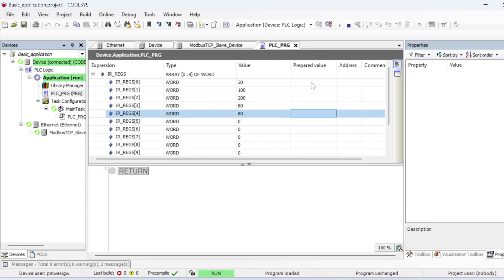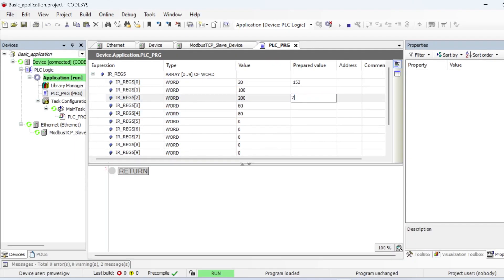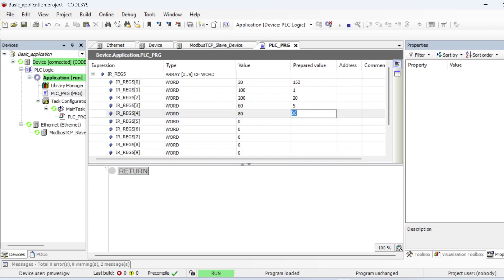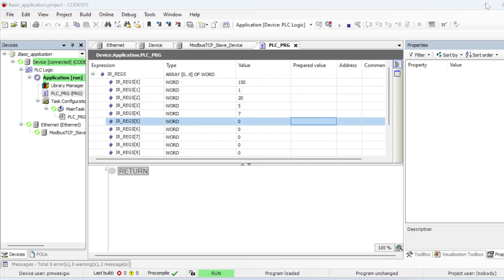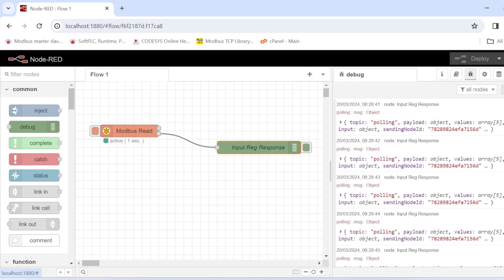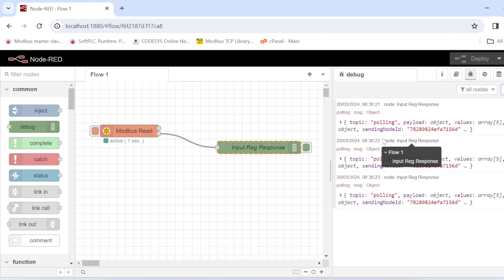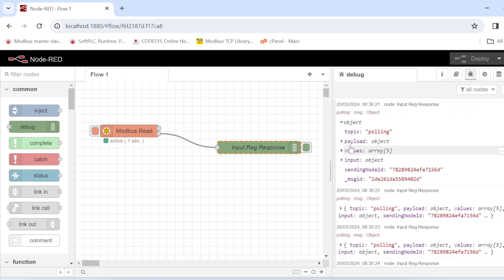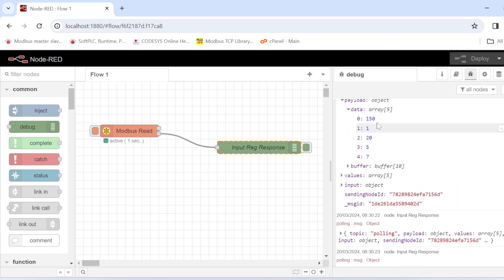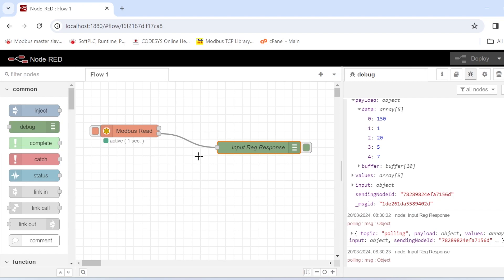We can modify values on the PLC side — for example, changing registers to 150, 20, 1, 5, and 7. Going back to Node-RED, clearing the messages and expanding the new payload, we can see under the data array the values 150, 1, 20, 5, and 7 — exactly matching what we set on the PLC. Everything is running correctly. This covers reading; we're reading only input registers here. We'll see other Modbus operations in other videos. Thank you and have a nice day.